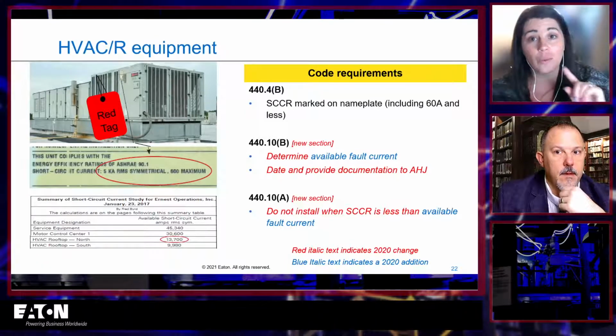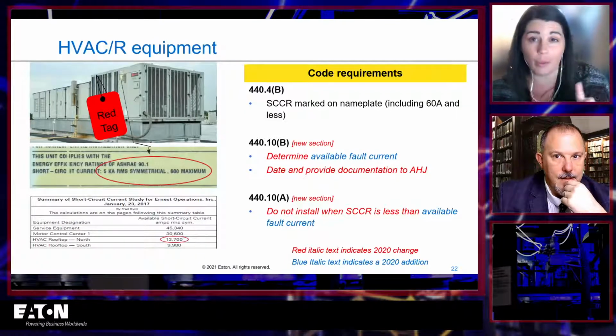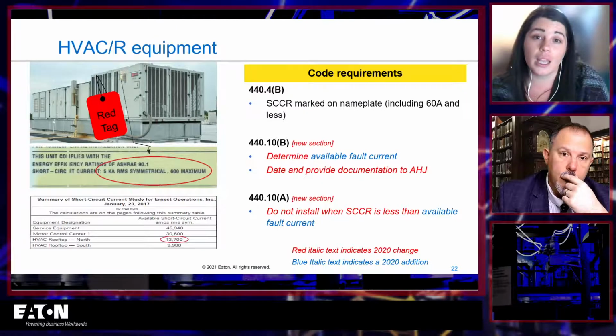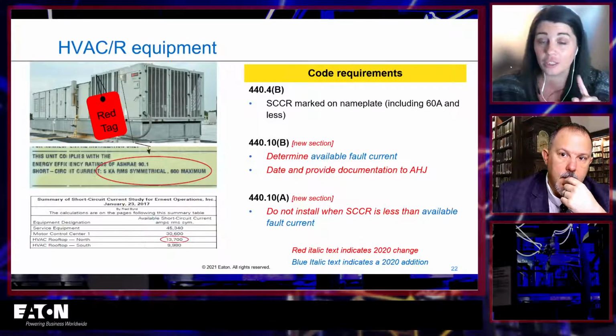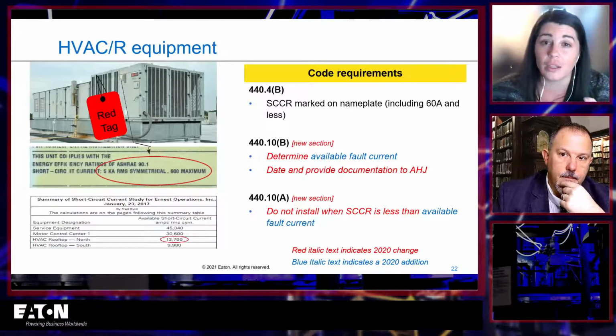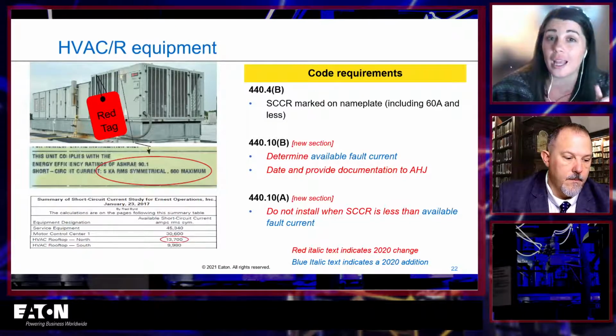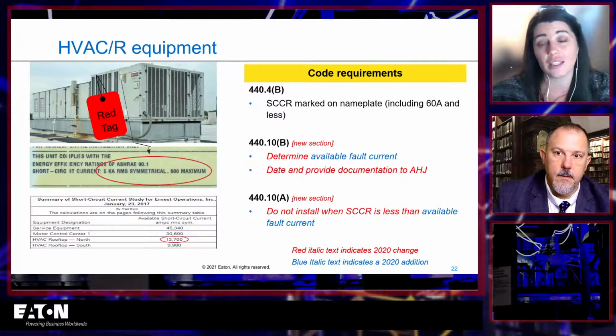Now this one is the one that I get the most phone calls about, probably of all of them. And a lot of it is, so there used to be exceptions to that SCCR marked on the nameplate. It used to be that if it were 60 amp or less, you didn't have to have an SCCR. Now the only exceptions that remain are if it's a single or two family home or if it's cord and plug.